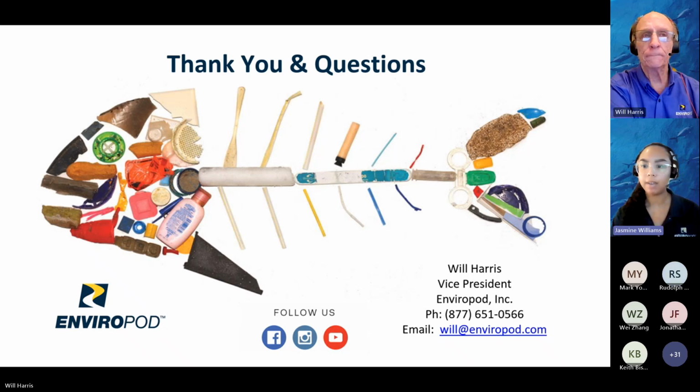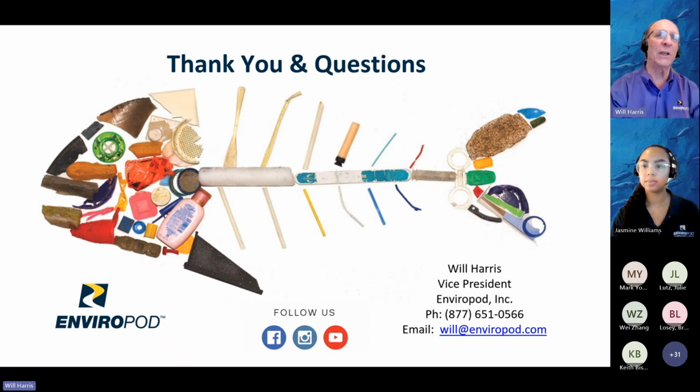Next question is, do you have any cost for labor effort estimates for maintenance in different sites? Well, typically it always takes two people to maintain any type of system, and we're talking about smaller type screens or inlet filter devices, MTDs, and safety factors also come in first. The time for two people to maintain on average an inlet filter could be anywhere from 5 minutes to 15 minutes with a Vactor truck or even by hand.